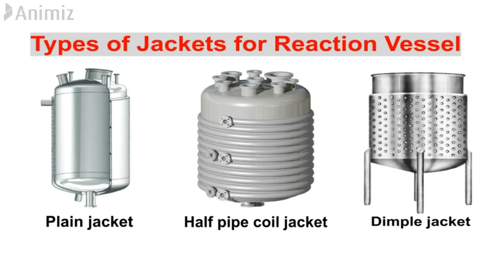Dimple jacket: this jacket style is approved by National Board of Boiler and Pressure Vessel Inspector up to 300 psi (21 kg per cm²). Useful for high jacket pressure operation, can induce turbulence even at very low flow velocity. These are used for high capacity vessels and where high velocities for circulating hot oil and glycol is required. In this jacket, bypassing and short circulation is completely avoided.